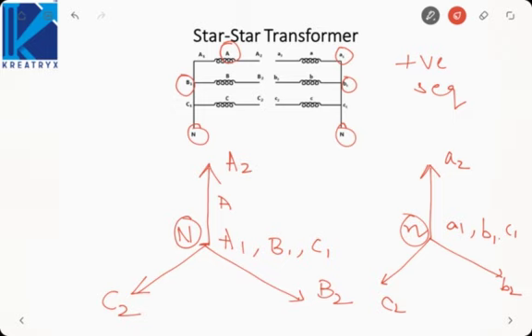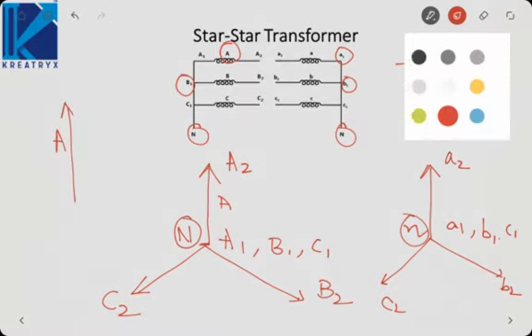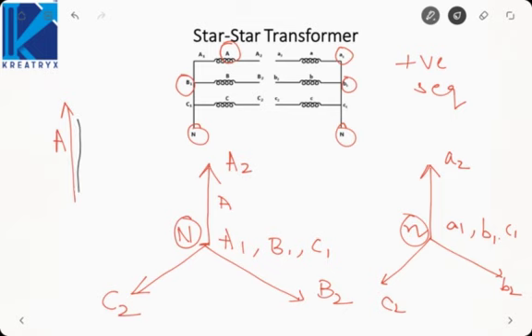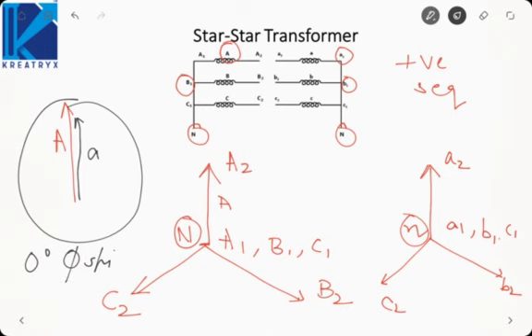Now if we denote both the phasors on a clock, A is vertical and small a is something like this. Now since both the phasors are coinciding, we have a 0 degree phase shift, which implies it is a YY12 connection. On the clock it seems as if 12 o'clock is the time, so it will be YY12. Y denotes star, capital for primary, small for the secondary winding. So this type of connection has been named YY connection.